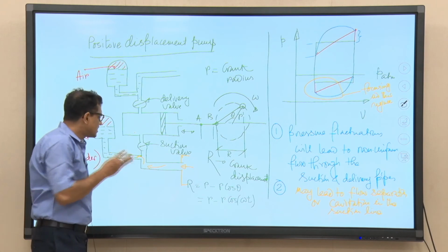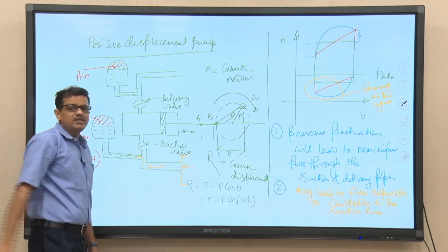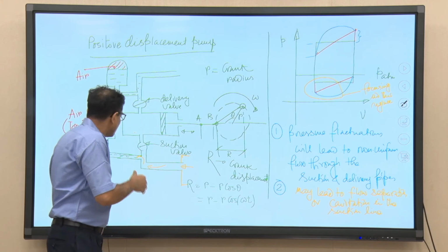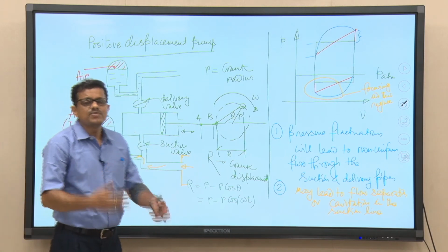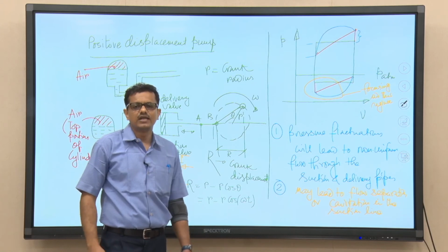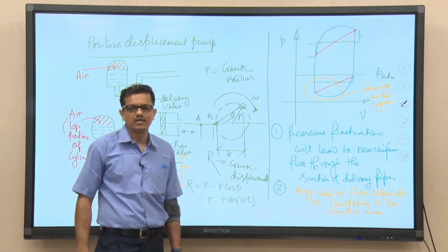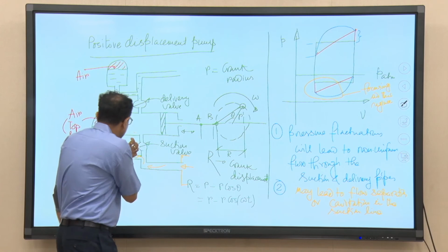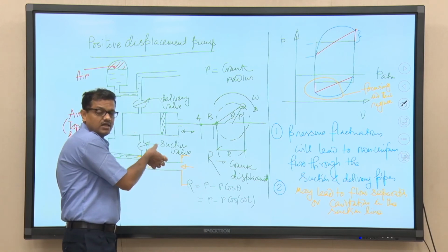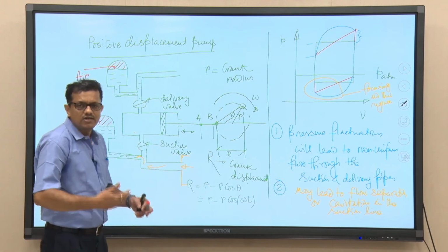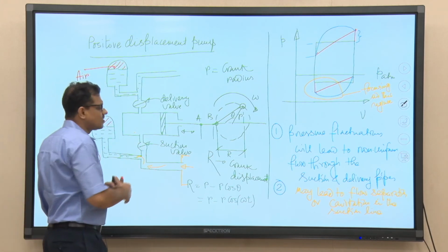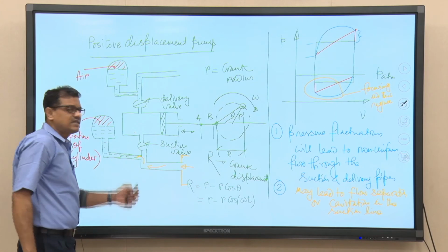Number 2, when the air chamber is connected, the problem of cavitation can be avoided; cavitation or separation will not be there. So, it will save the suction pipeline, and it will make the flow smooth, not fluctuating. So, this is all about the suction pipeline. Now, what about the delivery pipeline? Let us first talk about the suction side air chamber.